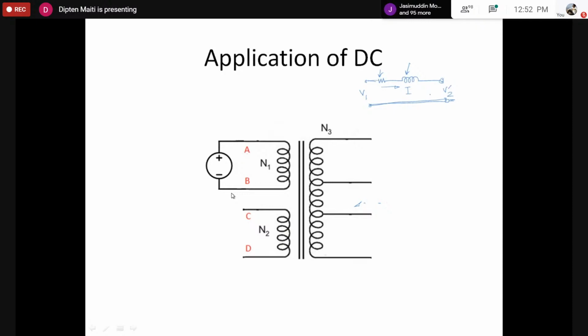Now, to behave as a good voltage source, the voltage drop across the resistance and the leakage reactance must be as low as possible. So the reactance value and the resistance value both must be as small as possible. Usually for a transformer, this is given by the voltage drop at the rated current, considering the phasor notations. The drop across the resistances and reactances in total is of the order of 5% for a well-designed transformer, and in some special cases it may be higher. However, that is deliberate because that is the requirement. Otherwise, for a well-designed transformer, that voltage drop is very small, of the order of 5%.